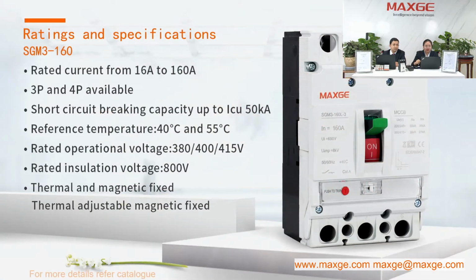The second one is the SGM3-160. The rated current is from 16 to 160, and here you have 2 choices: the first is the fixed type, and the second is the thermal adjustable, magnetic fixed type. The breaking capacity can be up to ICU 50K, because we have the L type and the M type, which have different breaking capacities. For this frame we have the connection with the box clamp. Next year we will have a very good MCCB in the 160 and 250 ampere frame, with many more benefits over the current existing range. The new frame will be launched next year.